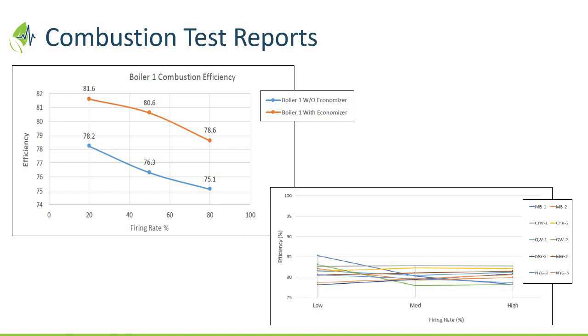That curious looking chart at the bottom there is one of the comparisons we do. That's a whole bunch of different hospitals. So as you're doing this testing, and again, Thermogenics and Southlake are going to be doing the testing once they have enough load on the boilers. Please don't test them under light loads because you just can't get reliable information. We can compare hospitals with each other. We can tell your individual boilers how they relate to each other, and we can tell you how your hospital compares to other hospitals.